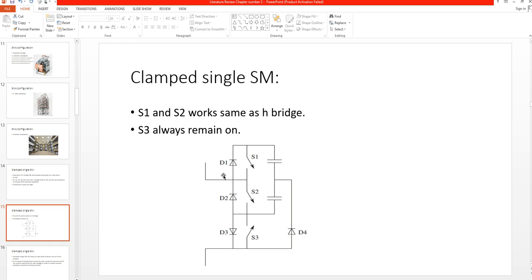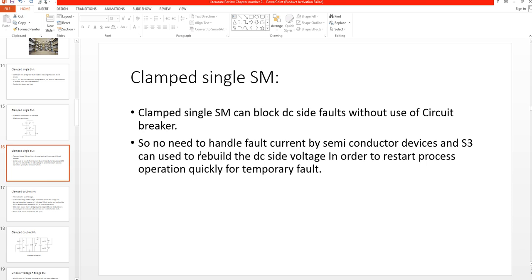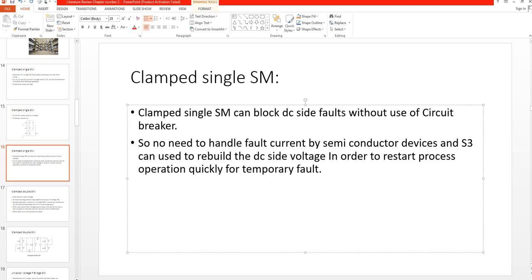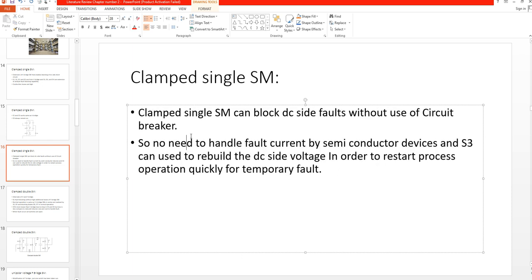The key features of the clamped single submodule topology are: it can block DC side faults without use of a circuit breaker, there is no need to handle fault current by the semiconductor devices, and S3 can be used to rebuild the DC side voltage in order to restart process operation quickly for temporary faults.